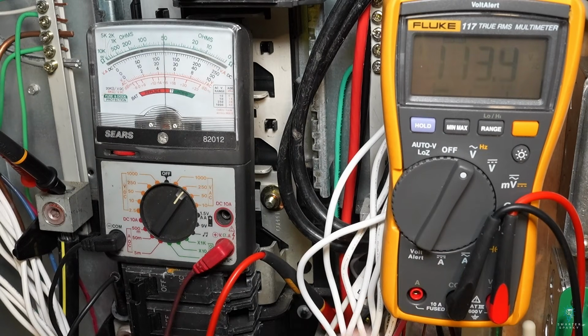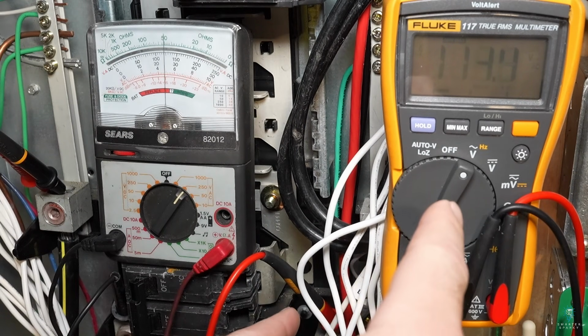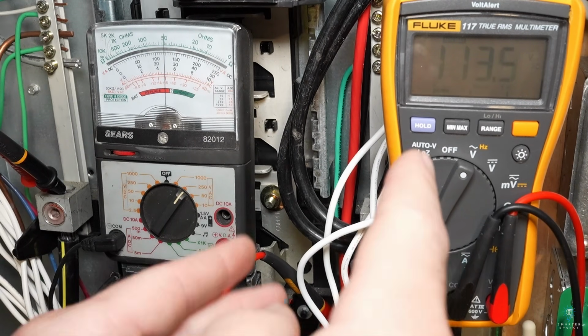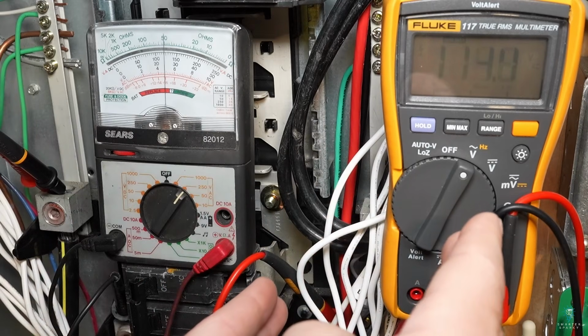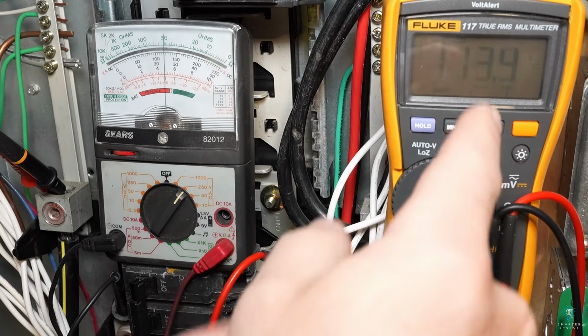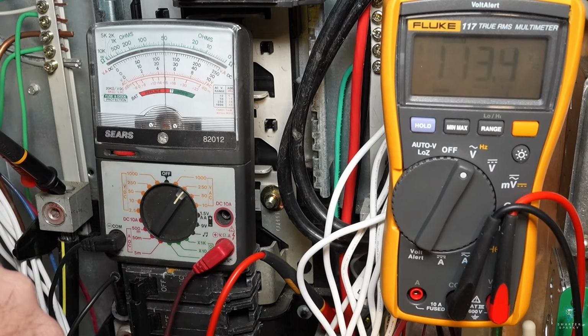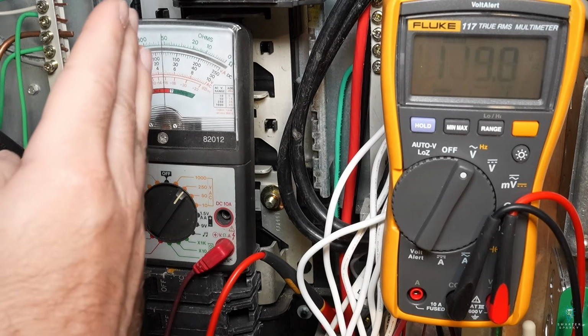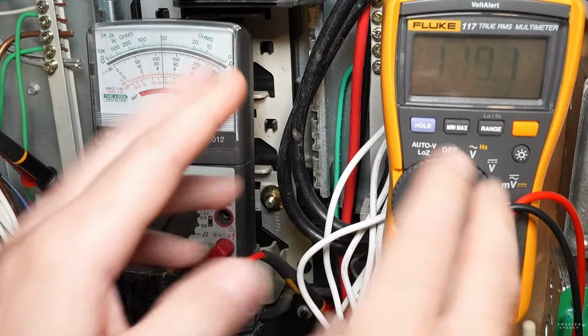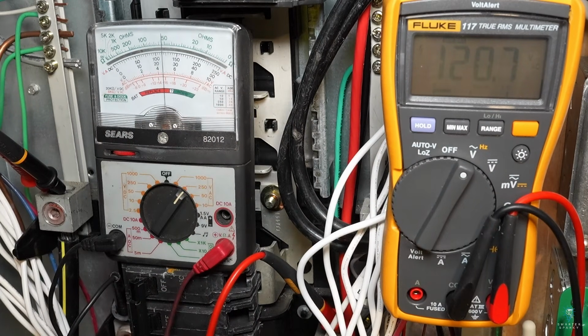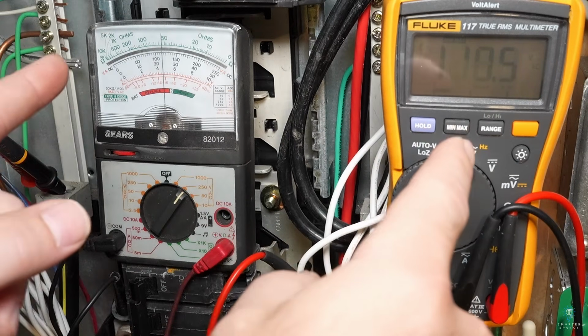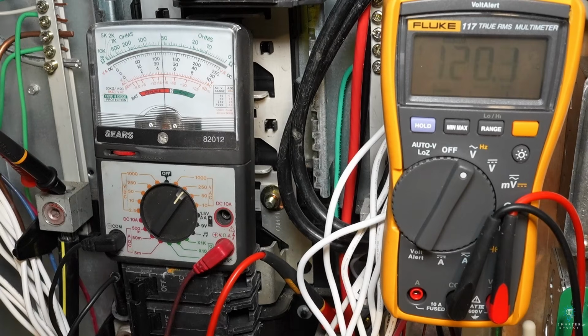What that means is whatever is on line 2 has created a higher load, so there's a higher amperage on line 2 now, and that's creating a voltage drop relative to neutral. On line 1, the voltage increased because of that extra weight on line 2. And now we're back down, that needle dropped back down. I'm guessing that is probably the sump pump kicking in.